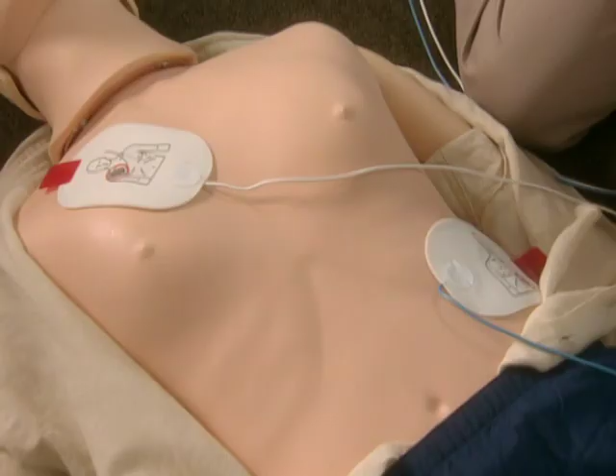The HeartStart home defibrillator is designed to be extremely easy to maintain. As soon as the battery is installed, the device begins a daily schedule of self-tests to ensure its readiness for use. If a problem is detected, or the battery power is running low, or the SmartPads cartridge is not functioning properly, then loud chirping will alert you. Also, the green ready light turns off, and the blue i button flashes. Press it for more specific information.